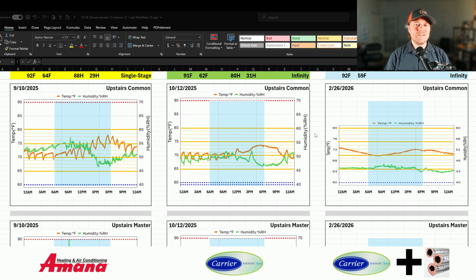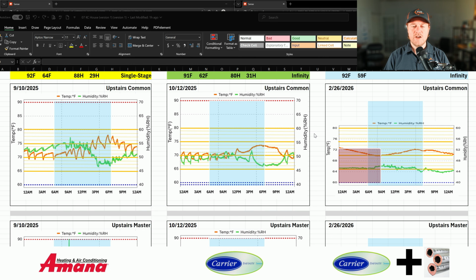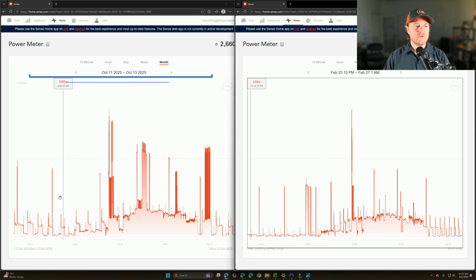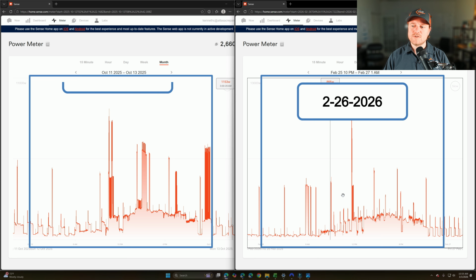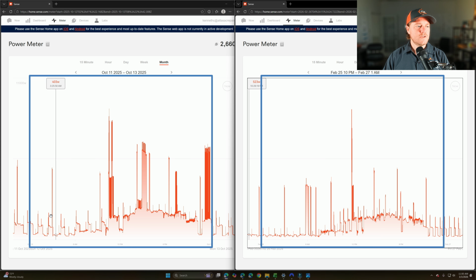However, in the morning, we can see that the indoor temperatures are still coming down, and in this time frame, the system's not even running, but the temperatures are still coming down. And we can see an example of the system not running from my power meter. Here we have October the 12th, and over here we have February the 26th. And over here in October, you can see at midnight how the system continually cycles on and off all the way up until 12 p.m. Then it runs for a really long time from there.